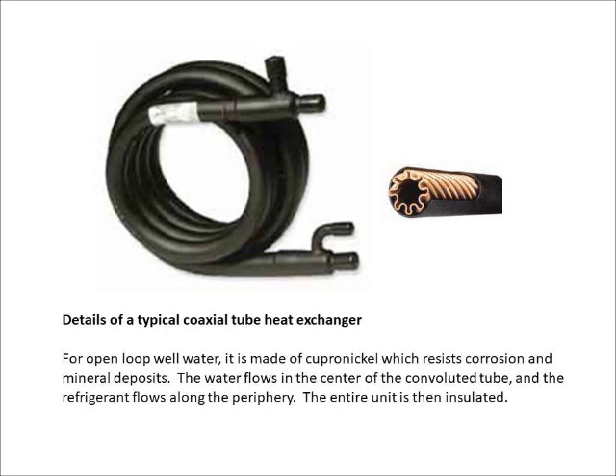These views show the details of a typical coaxial tube heat exchanger. For open loop well water, it is made of copper nickel, which resists corrosion and mineral deposits. The water flows in the center of the convoluted tube, and the refrigerant flows along the periphery. The entire unit is then insulated.